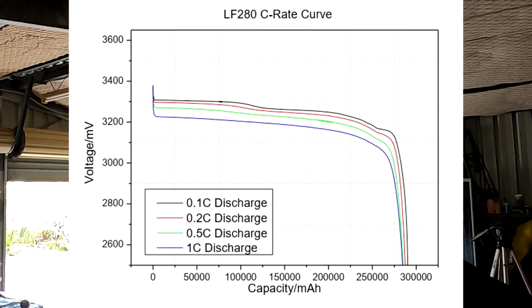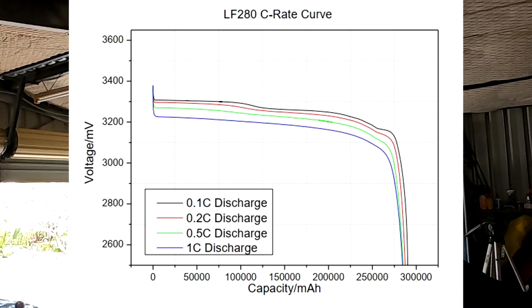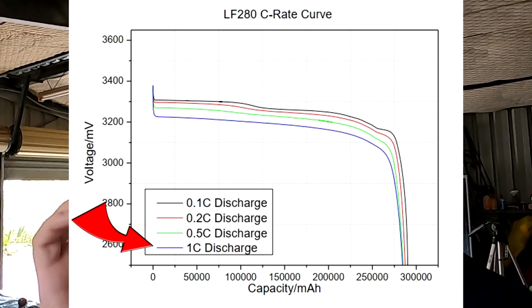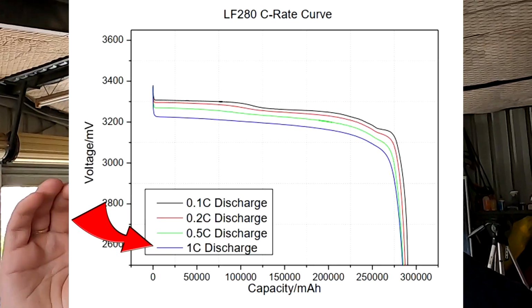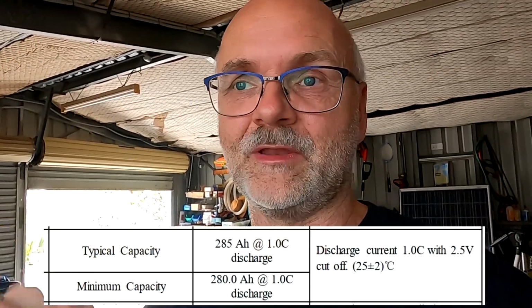Looking at the specifications and discharge graph supplied with these cells, you can see they did the discharge of 285 ampere hours at 1C, a super high current of 280 amps. Usually batteries don't perform that well at such high amperages, because internal resistance and internal heat loss increase a lot, giving far less capacity. But they are confident they get 285 ampere hours out of the battery even at 1C.